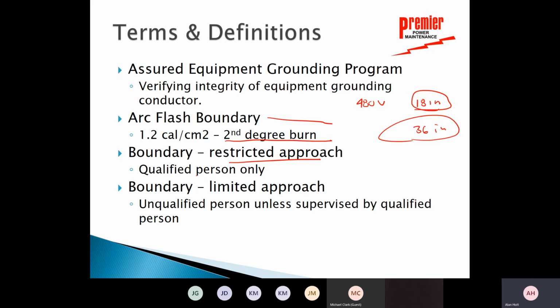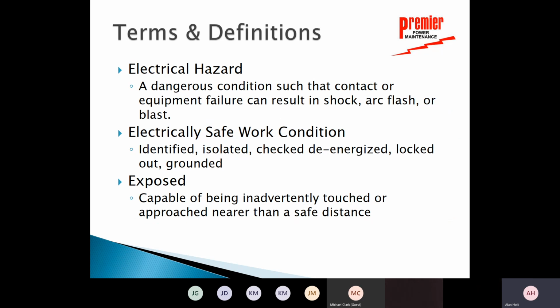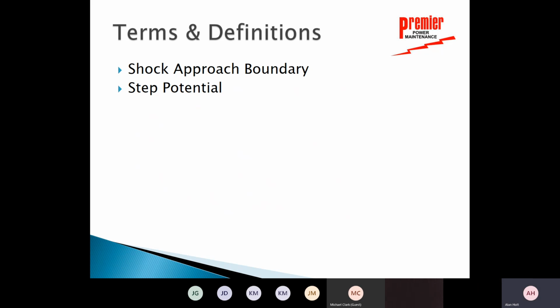Restricted approach, we've mentioned before, qualified person only. Limited approach, unqualified person unless you're supervised by a qualified person. So you could get inside that limited approach boundary if you were supervised by one of our qualified people. Electrical hazard is a dangerous condition such that contact or equipment failure could result in a shock, arc flash, or an arc blast. So these are definitions that they've developed in their policy. Electrically safe work condition means identified, isolated, checked, de-energized, locked out, and grounded. Okay. Exposed, capable of being inadvertently touched. So anytime you can get closer or could inadvertently touch something, that would be cause for exposure.